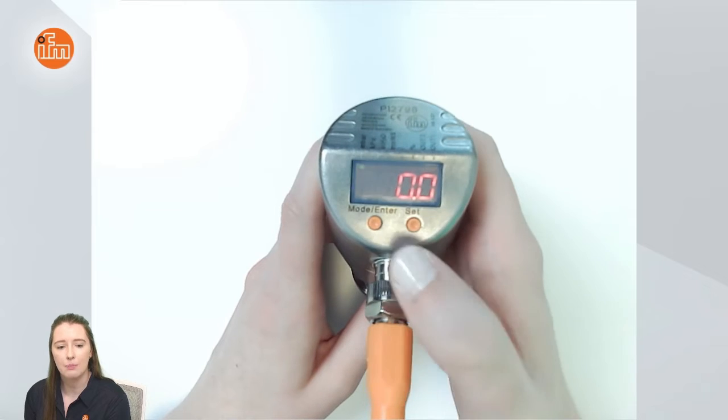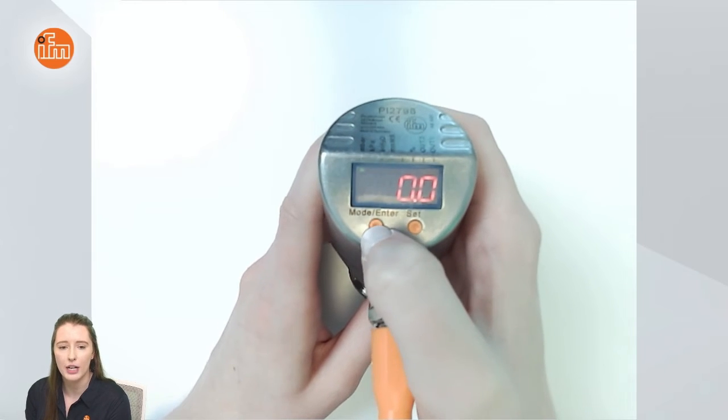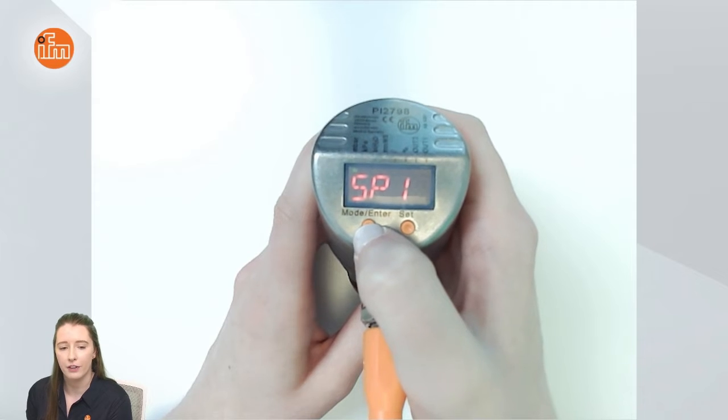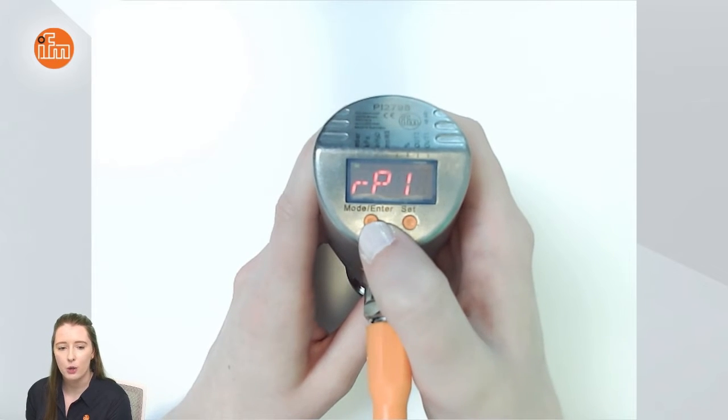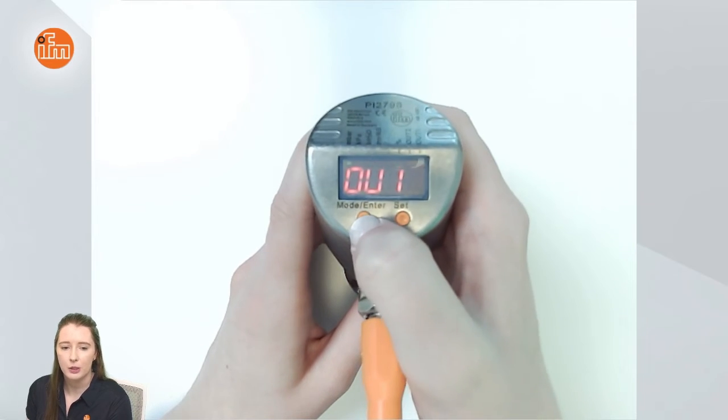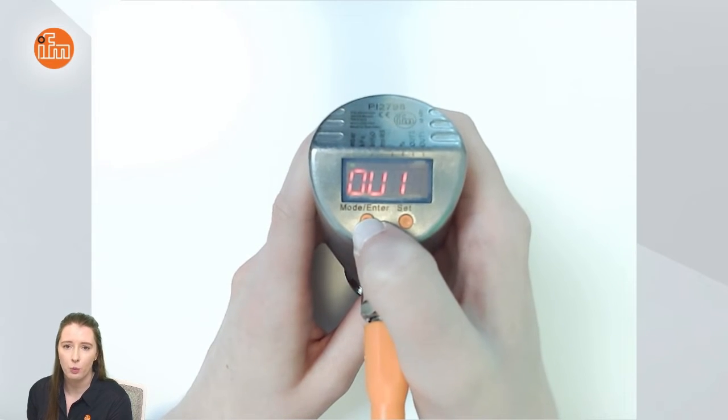So to begin to get into the menu structure you would press the mode enter button. Here you see sp1 which is your switch point for output 1. If you press mode enter again you would see rp1 for your reset point for output 1. If you press mode enter again you'll see output 1 which is where you can change your output 1 mode.